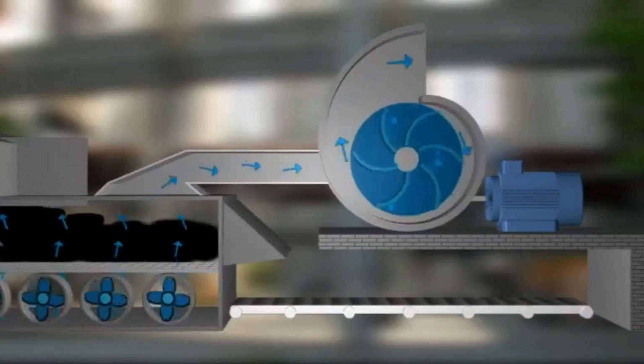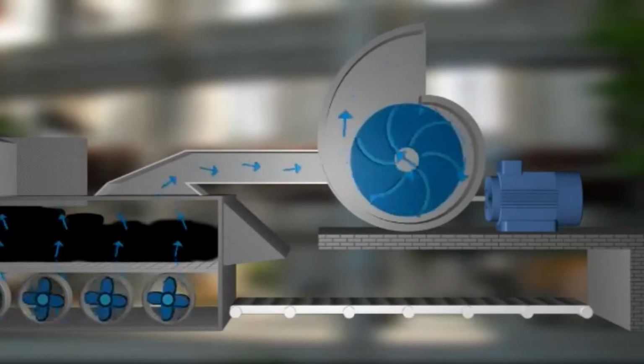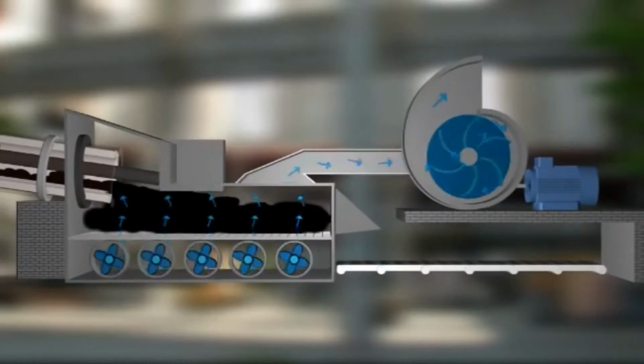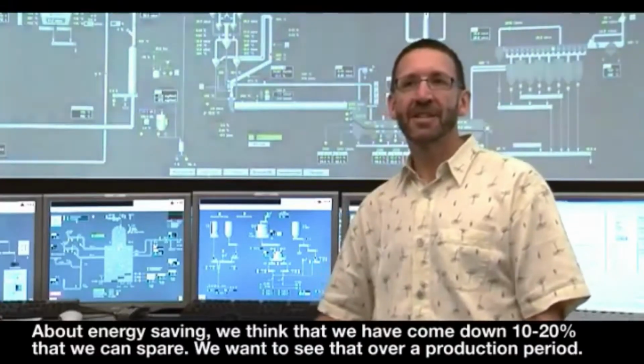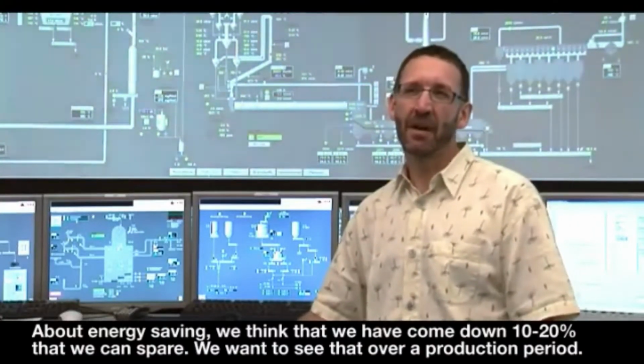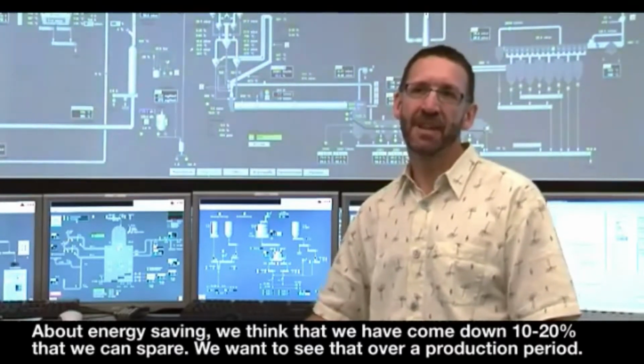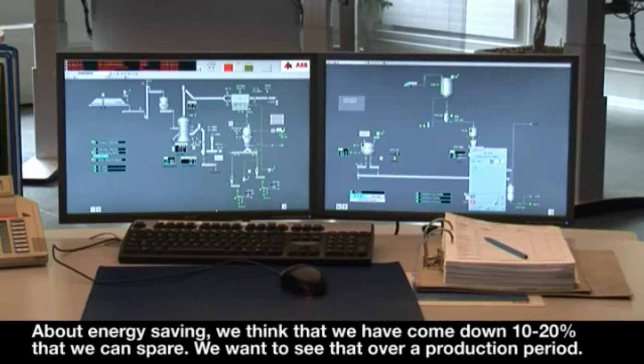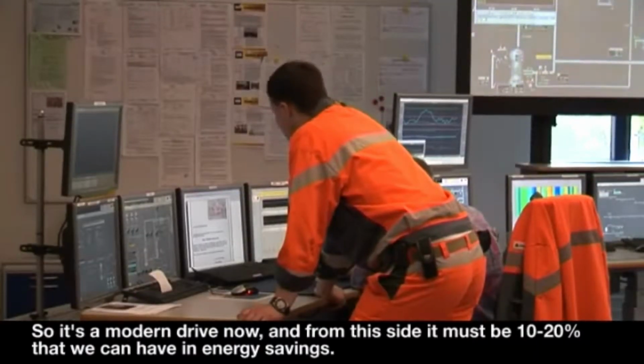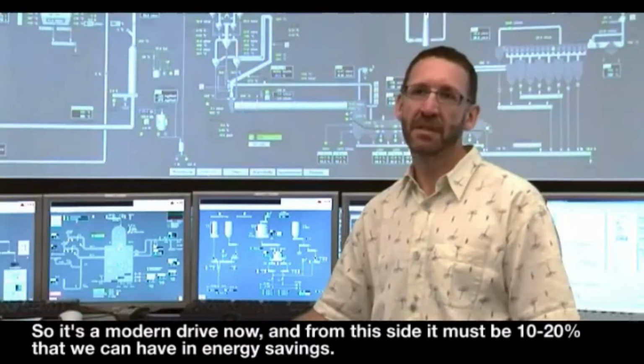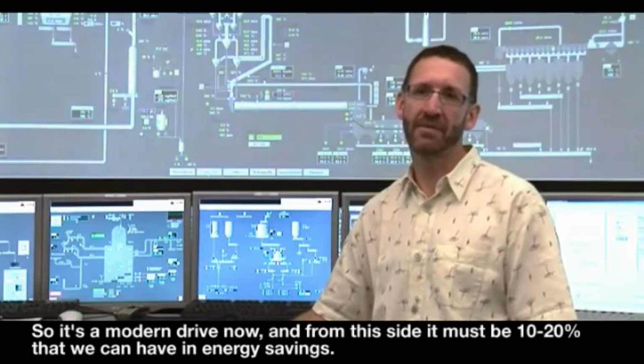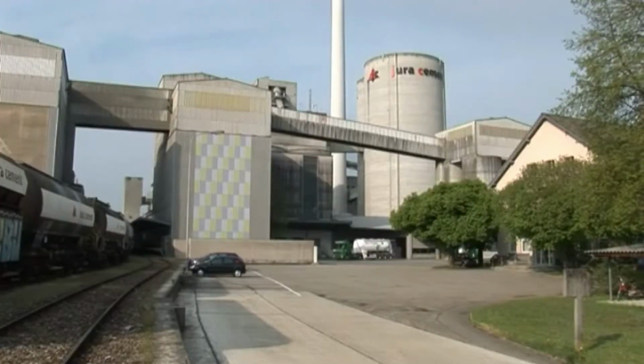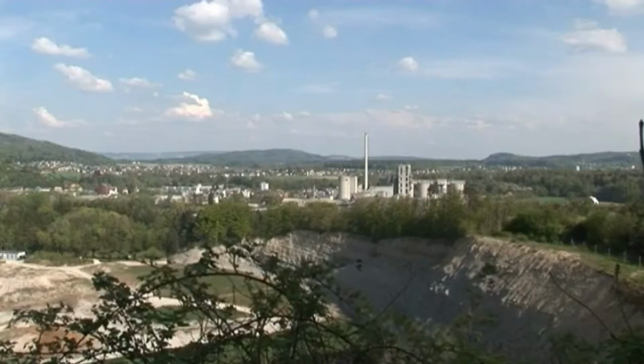The kiln exhaust fan is one of the largest consumers of energy in a cement plant. Controlling a kiln exhaust fan with an electric variable speed drive can result in significant energy savings. Jura Cement and ABB are planning to monitor the energy consumption and compare this against that consumed by the Cascade drive. About energy saving, we think so that we come down 10-20% that we can spare. We want to see that over a production period. So it's a modern drive now, and from this side it must be 10 to 20% that we can have energy savings. According to them, the cost of the drive can be easily recovered from energy saving alone.